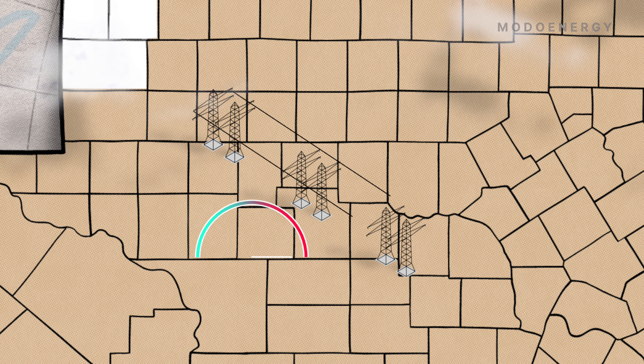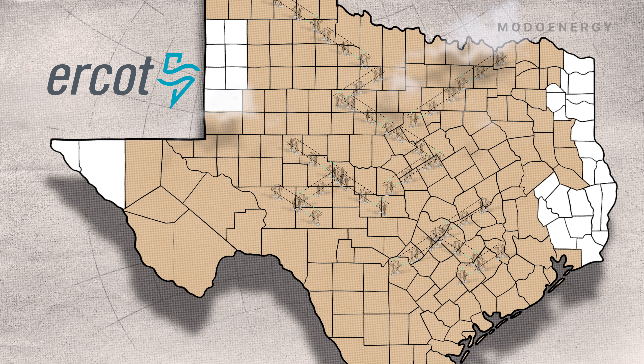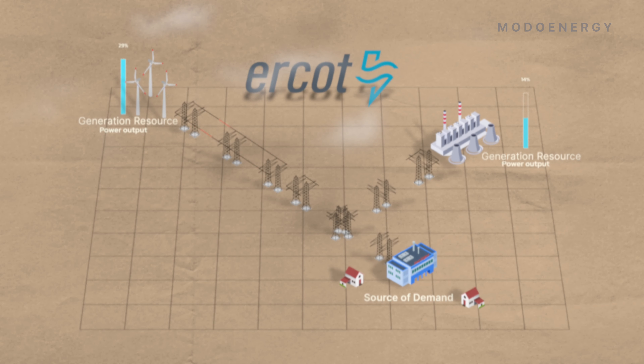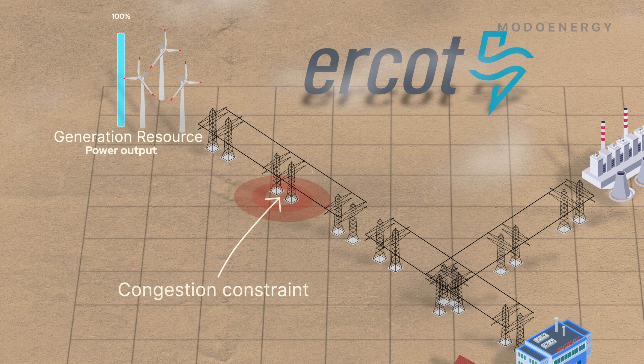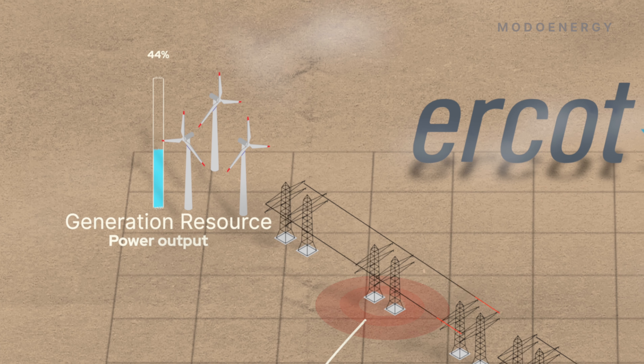To protect equipment, ERCOT monitors the power flowing across all elements in the transmission network. In ERCOT, congestion is the cause of price disparity between settlement points. When congestion occurs, ERCOT needs to take action. Usually, this means re-dispatching generation to reduce the amount of power flowing across the congested part of the network.